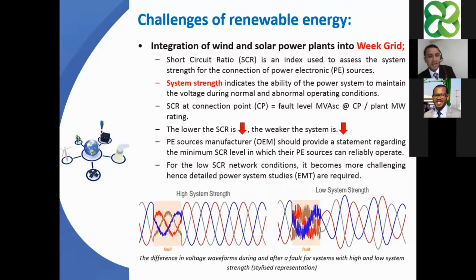So to achieve this properly, that requires the grid to be strong. So what's going to happen if we integrate our wind or solar power plants into a weak grid? Then we need to introduce something we call system strength, which indicates the ability of the power system to maintain the voltage during normal and abnormal operating conditions. And to quantify how strong the network is, we have what you call the short circuit ratio. In short, it's SCR, which is an index used to assess the system strength for the connection of power electronic sources.